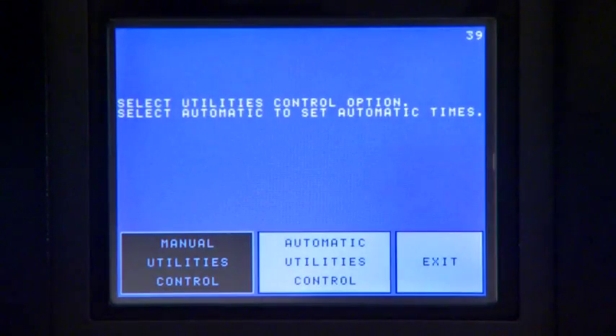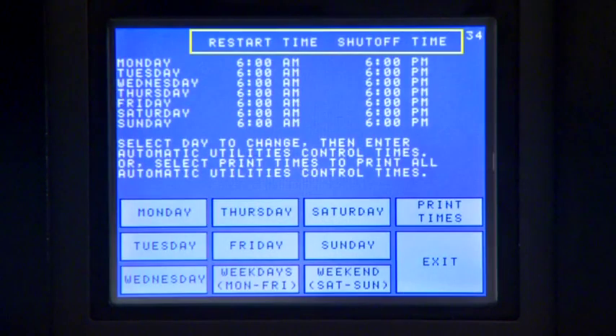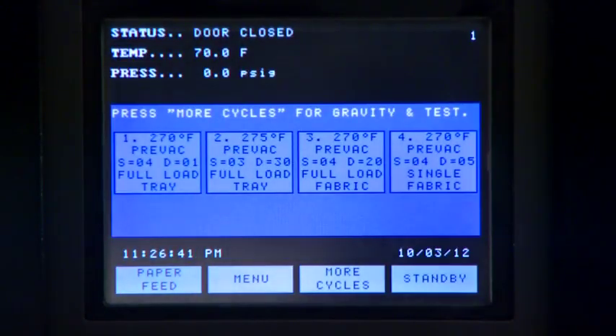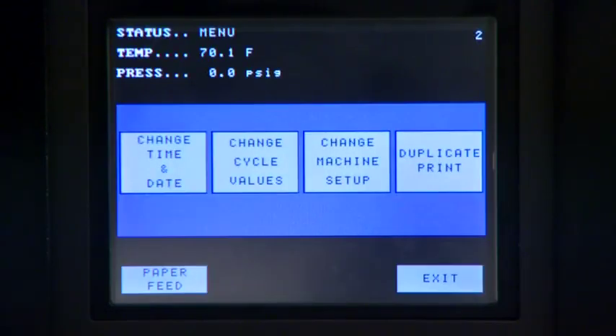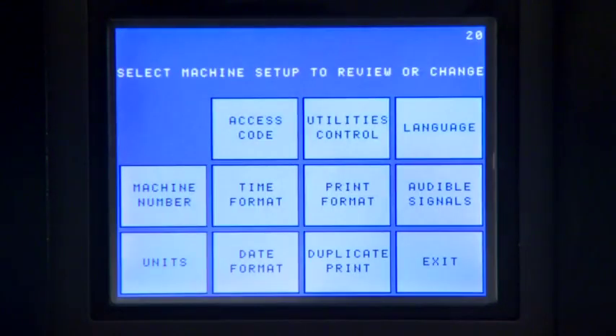You can also use the Auto Utility controls to program the sterilizer to automatically shut off its steam and water at the end of the day to conserve utilities. Shutdown and power-up times can be programmed for any time of the day on weekdays or the weekend. To set up this function, press the Menu button from the main status screen. Press the Change Machine Setup button, then the Utility Control button.